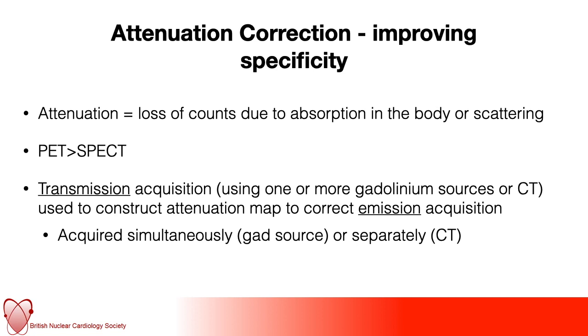Attenuation is the loss of counts due to absorption or scattering within the body. It is a much bigger issue in PET than in SPECT because PET requires simultaneous detection of two photons — coincidence detection — so any attenuation has a much greater impact. This is why CT is obligatory in PET, hence why it is always abbreviated as PET-CT. The transmission acquisition is used to construct an attenuation map, which is then applied to correct the emission acquisition, improving specificity.